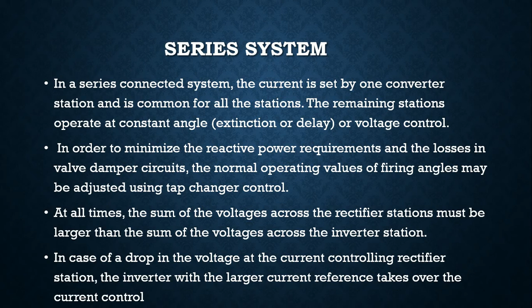At all times, the sum of the voltages across the rectifier stations must be larger than the sum of the voltages across the inverter stations. In case of a drop in the voltage at the current controlling rectifier station, the inverter with larger current reference takes over the current control. Let us see about the parallel system.